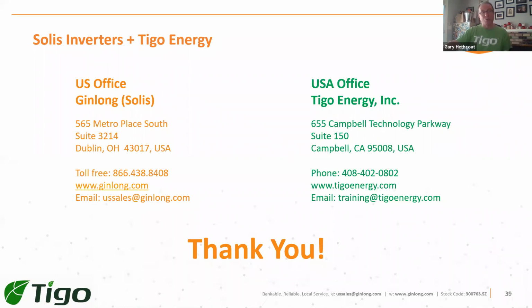That is for the wireless products. The TS4F, as in fire safety, does not apply. It has to be deployed 1 per module on the entire system with no other kind of Tigo. So the TS4F is a special product because it uses power line communication. It needs to be deployed across the entire system. So that's how the selective deployment works.